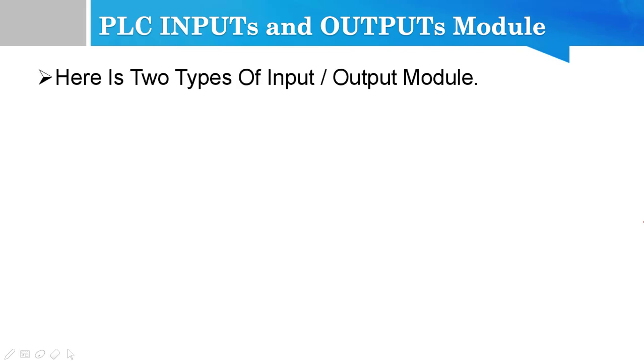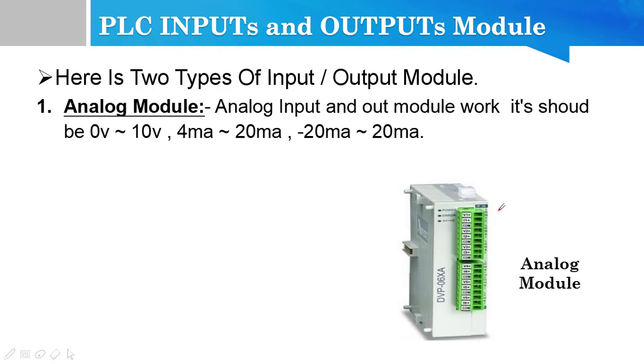Here are two types of input and output modules. As you can see here, I have shown an analog module here. Analog module inputs and output modules work with 0 to 10V, 4mA to 20mA, and minus 20mA to plus 20mA.